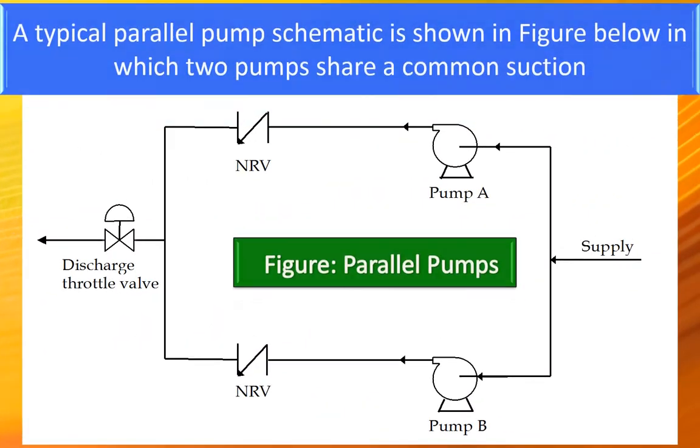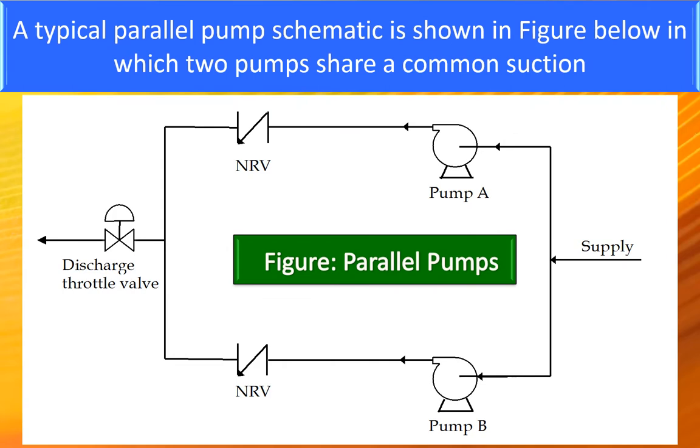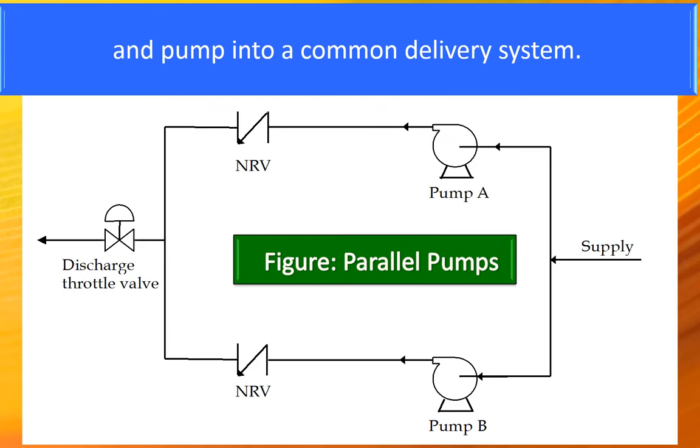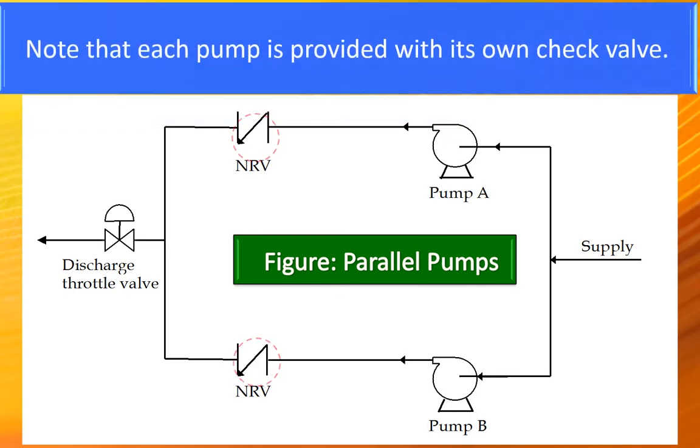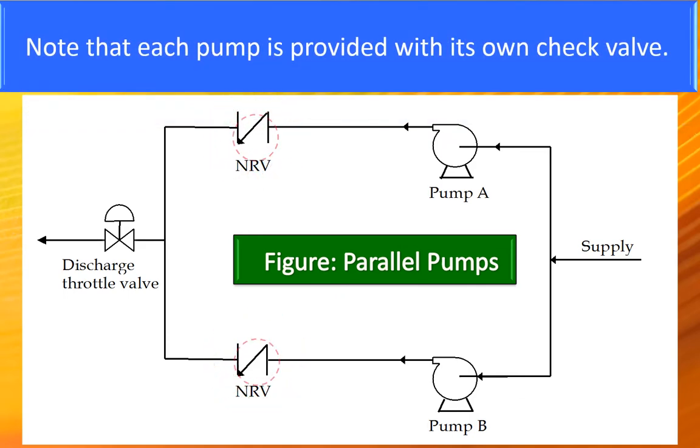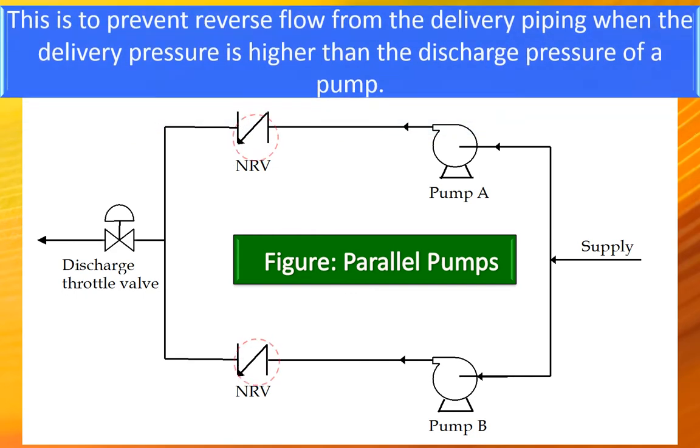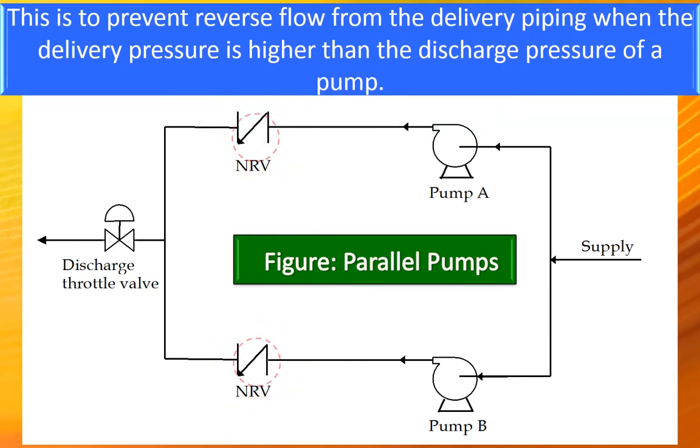A typical parallel pump schematic is shown in the figure below in which two pumps share a common suction and pump into a common delivery system. Note that each pump is provided with its own check valve. This is to prevent the reverse flow from the delivery piping when the delivery pressure is higher than the discharge pressure of a pump.